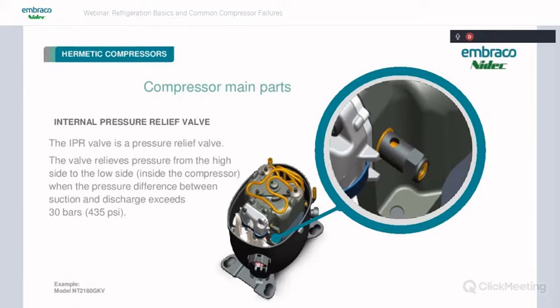It's going to make a pretty loud noise and hopefully cause the owner of the equipment to call for service. And basically what this is going to do is it's going to save the compressor from damage. And so hopefully the technician is going to come out, correct the reason for the high discharge pressure, and the compressor will still be perfectly operational afterwards. But it opens up under high discharge pressure, and once that pressure falls off, it's going to go ahead and reset and close.